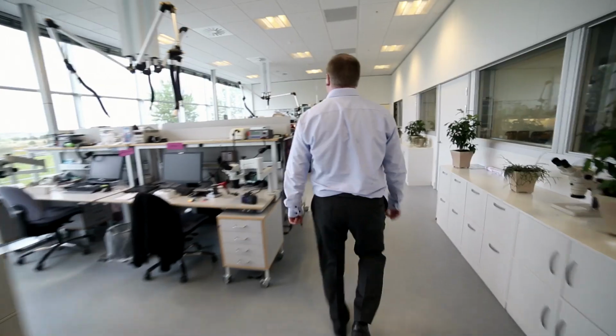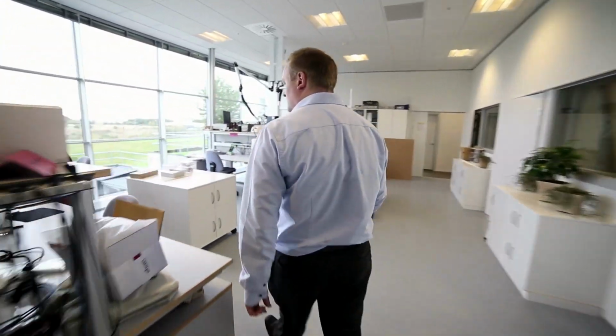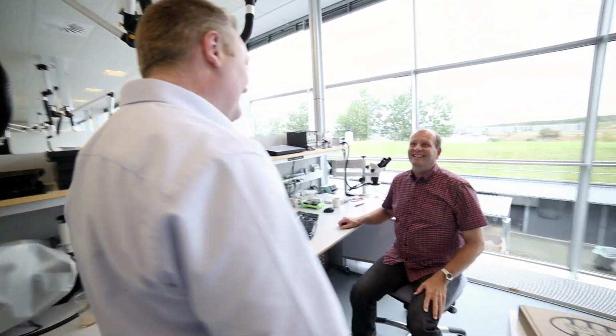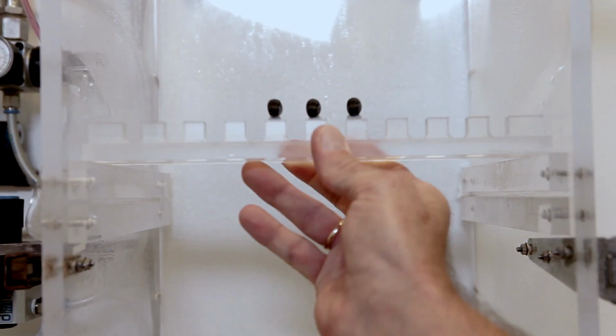The new custom program has been improved on several points, especially the transducer protection system - ProWax and OCAP - where the customer will feel the difference. We did the artificial earwax test and found that no wax entered beyond the protection system.